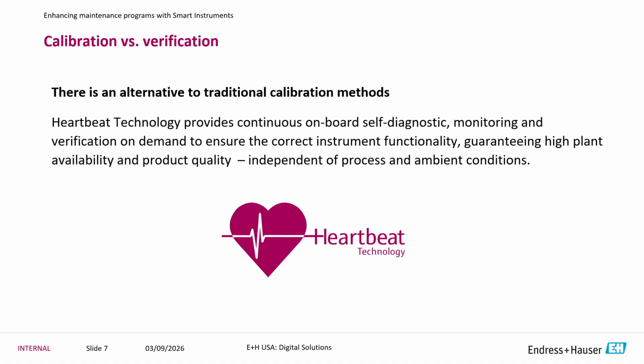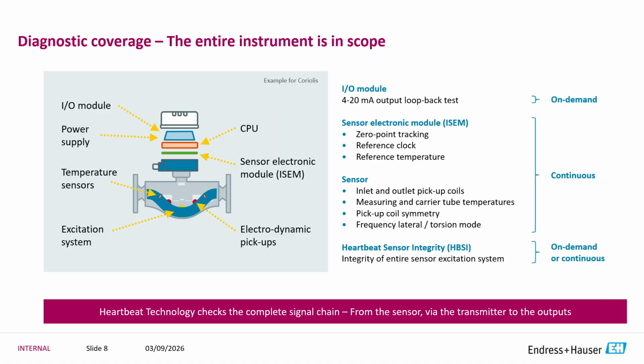So now we have some additional data in between those calibration intervals. This is the full diagnostics coverage of that verification. It's checking everything from the entire loop—the I/O module, the power supply on the transmitter, the pickup coils, and the excitation system of the Coriolis. So it's checking the entire meter. For us, this is a lot more valuable to have this kind of data set available in the interim. That's just Coriolis.